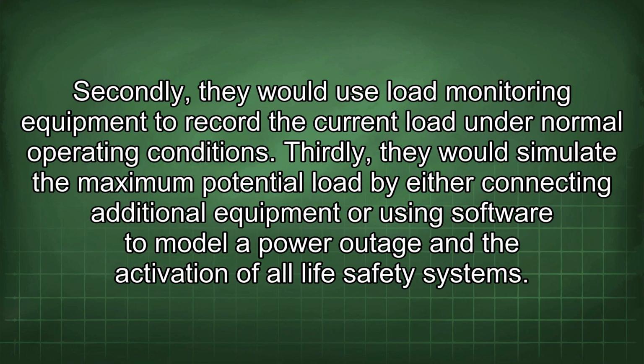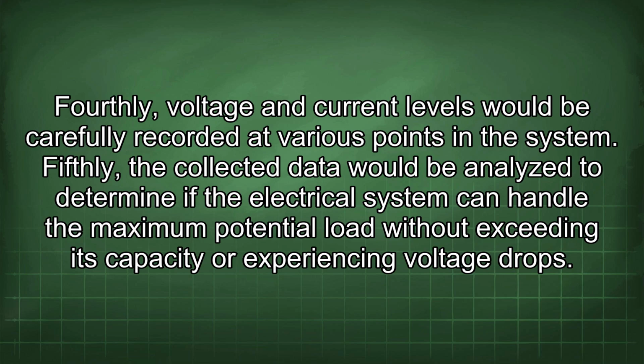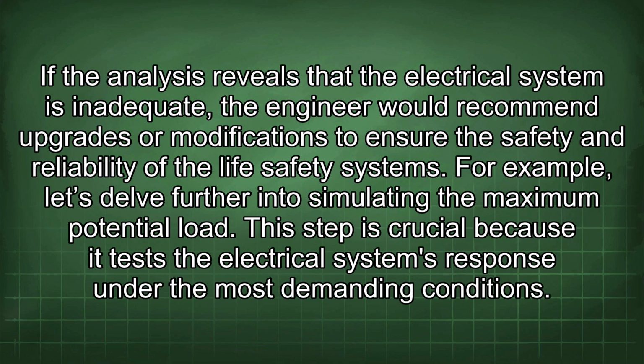Secondly, they would use load monitoring equipment to record the current load under normal operating conditions. Thirdly, they would simulate the maximum potential load by either connecting additional equipment or using software to model a power outage and the activation of all life safety systems. Fourthly, voltage and current levels would be carefully recorded at various points in the system. Fifthly, the collected data would be analyzed to determine if the electrical system can handle the maximum potential load without exceeding its capacity or experiencing voltage drops. If the analysis reveals that the electrical system is inadequate, the engineer would recommend upgrades or modifications to ensure the safety and reliability of the life safety systems.